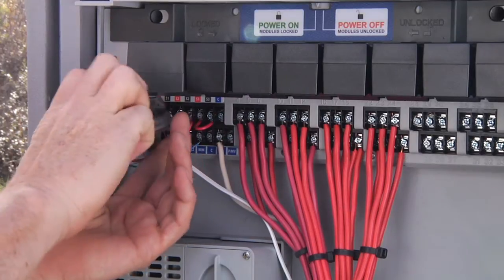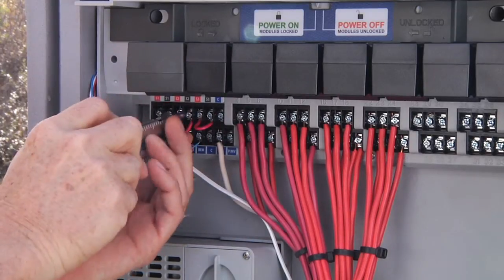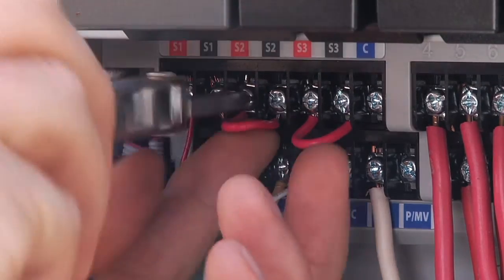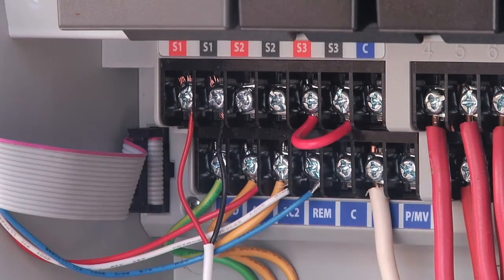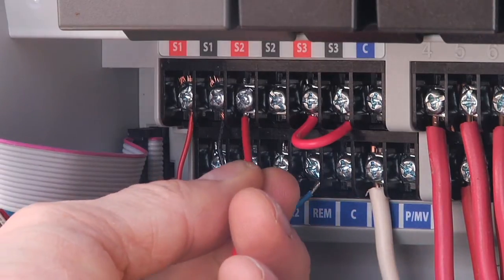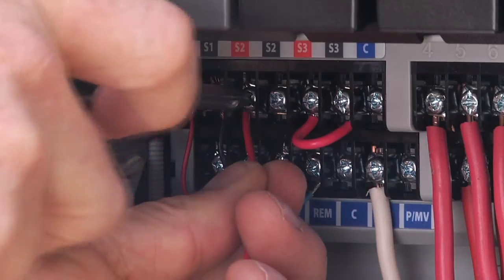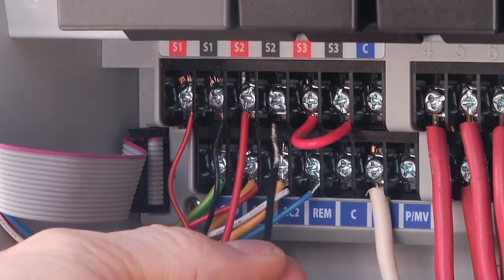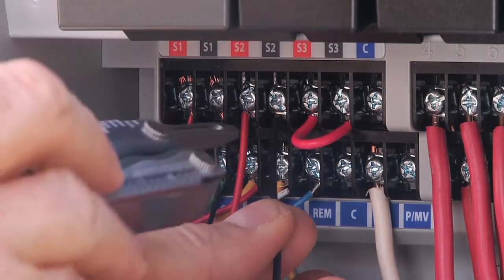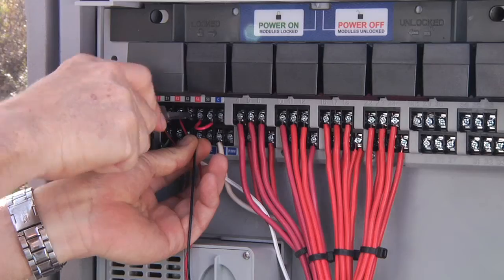one. We will connect our flow sensor to S2 because there is already a sensor connected to the first set of sensor terminals. The red wire goes to the red sensor terminal and the black wire to the black sensor terminal. If you have extended the flow sensor wiring with another cable, be sure to keep the red and black wires straight, or the sensor cannot be read.